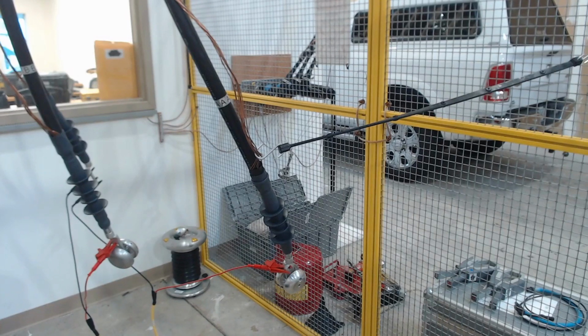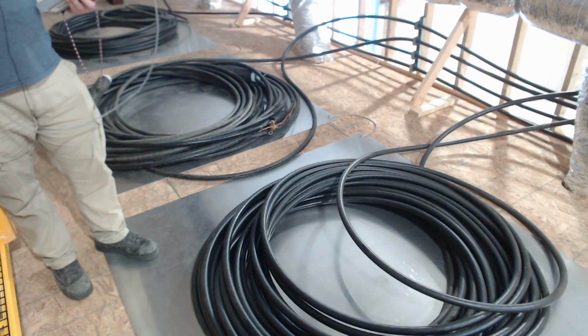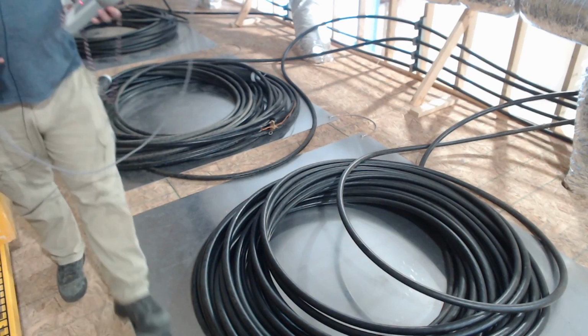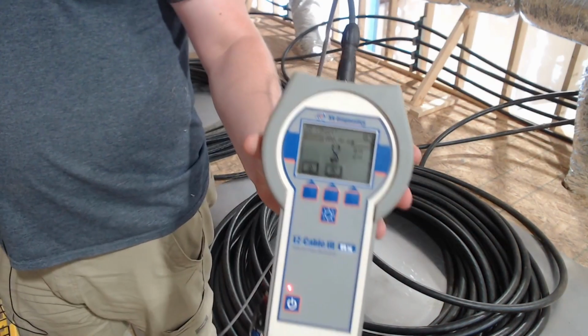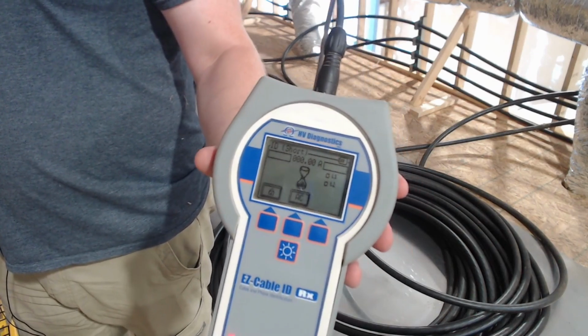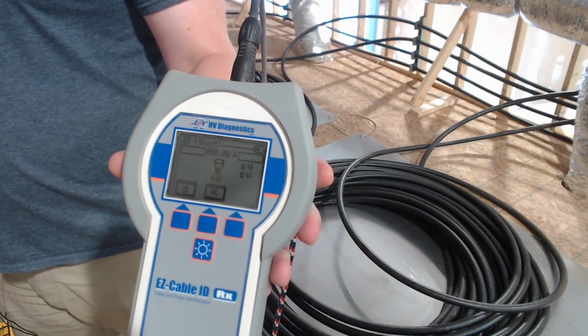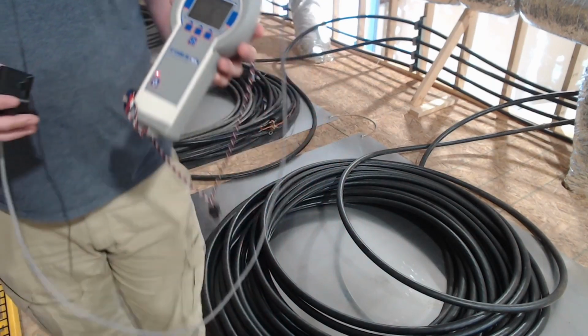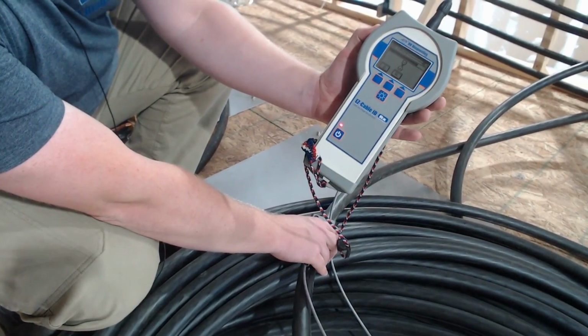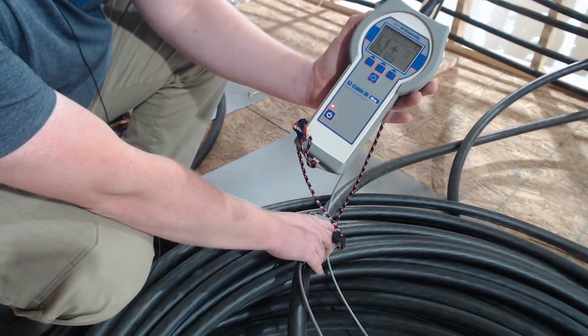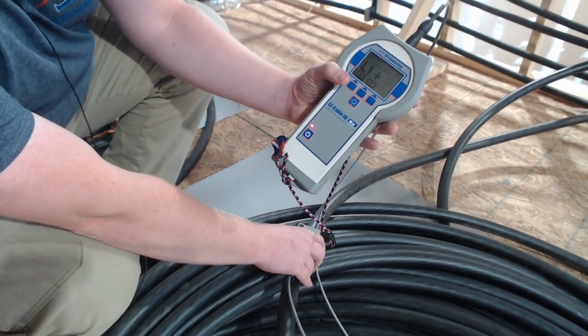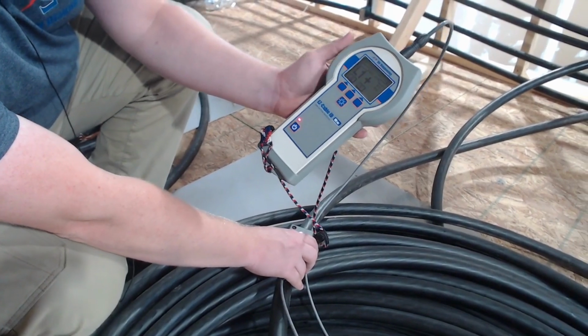So this will be our setup, and we will move up to the upstairs where the cables are coiled up, and we will read from there. We have our EasyID running and beeping on its 3-phase mode. So now we can take our EasyID. We are set to just identify mode, not doing the calibration. So we'll just come up here. If you want to follow with the camera, Cody. So it's telling us this is L1. We're getting about 3 amps. So this is L1. So we're now on L1 here.